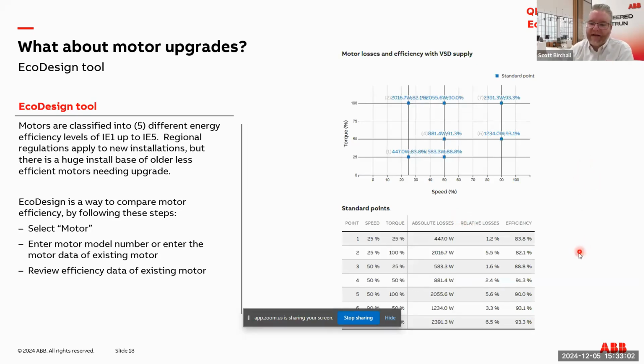What it does is tell you how efficient that motor is. At full speed, that motor is 93.3% efficient. There are all these different load points here. There's an industry standard, and that's why these load points were selected. This isn't just ABB picking load points; there's an industry standard that we went with. In HVAC, a common load point would be 50% speed, 25% torque. So I can now see that motor is only 88.8% efficient. I can also see my actual losses coming out of that motor here.